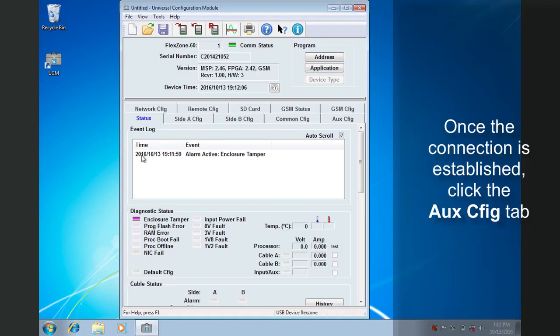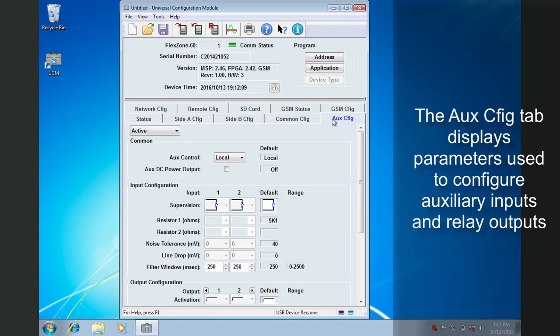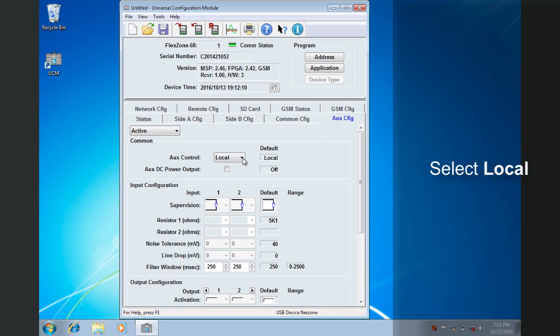Once the connection is established, click on the Aux Config tab. The Aux Config tab displays the parameters used to configure both FlexZone auxiliary inputs and relay outputs. In this video, we are focusing on the relays. First, in the Aux Control drop-down list, select Local. This configures the processor's inputs and relays to be managed by the processor itself, rather than from over a network.